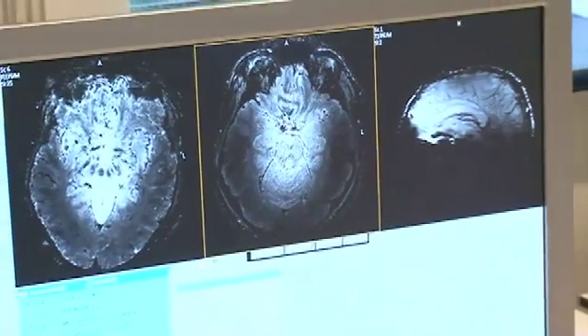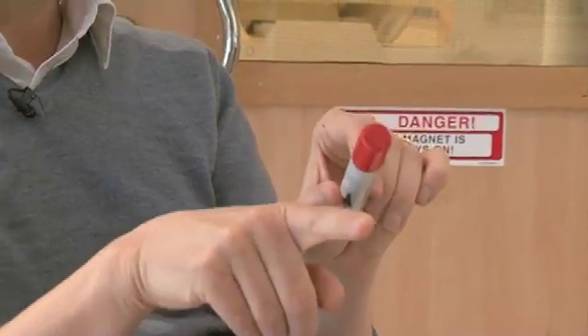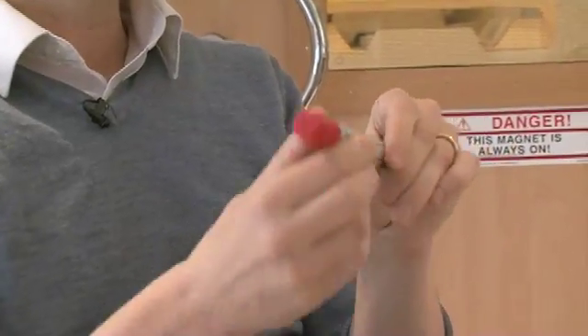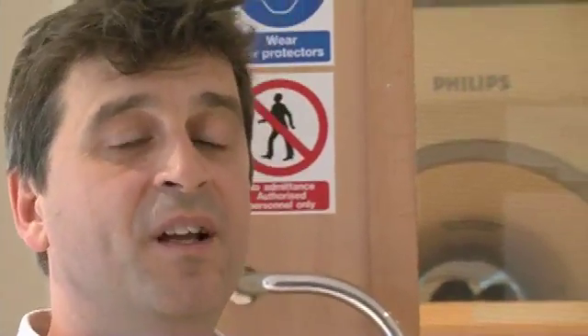These nuclear magnets have a property that when they get disturbed from being lined up with the field, they tend to precess around it. The rate at which they go around depends on how strong the magnetic field is. In this 7 Tesla system, they go around at about 300 million times per second — at 300 megahertz. That frequency is in the radio wave region of the electromagnetic spectrum, so there's a natural interaction between the hydrogen nuclear magnets and radio waves.